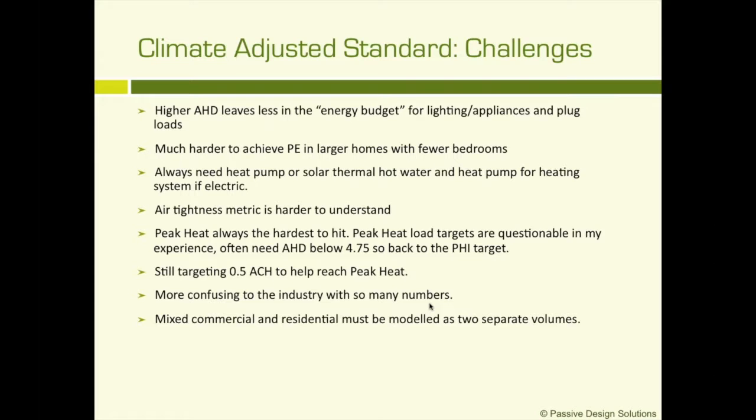We've been energy modeling a large number of projects and preparing a document to send to the PHIUS Tech Committee that makes an argument that in our climate, and we've modeled them in 7 climates in Canada, the annual heat demand usually has to go back down below 4.75 in order for us to hit the peak load.